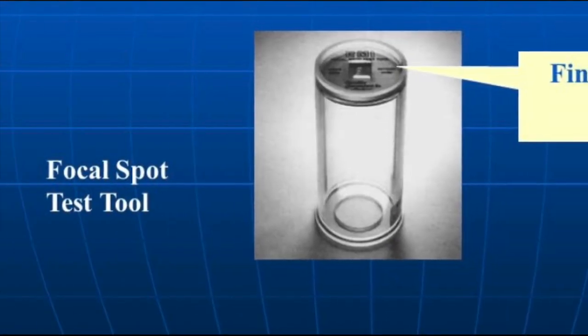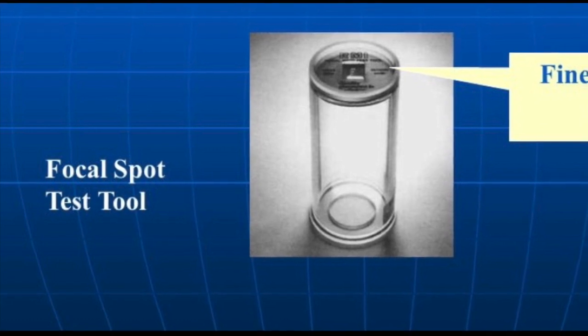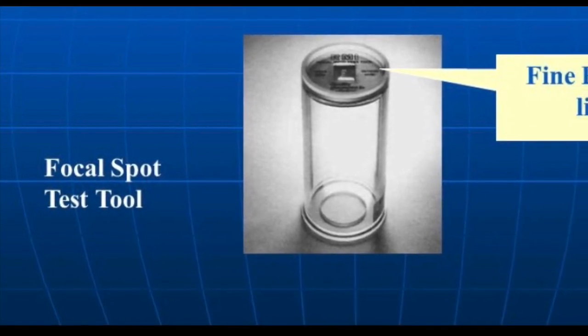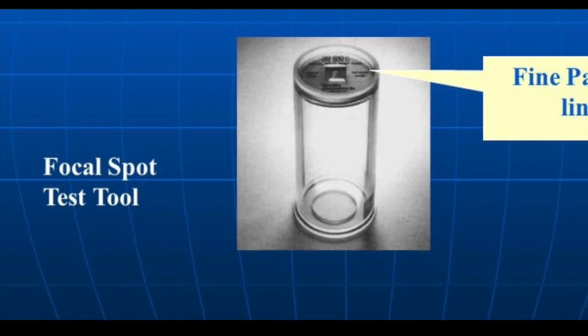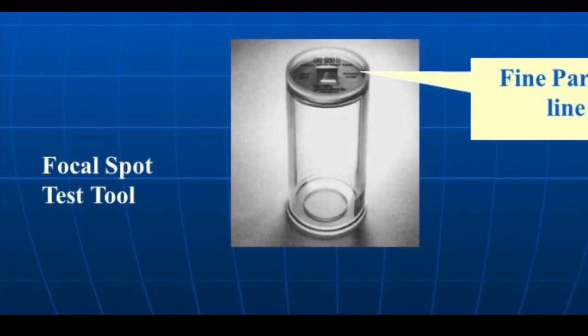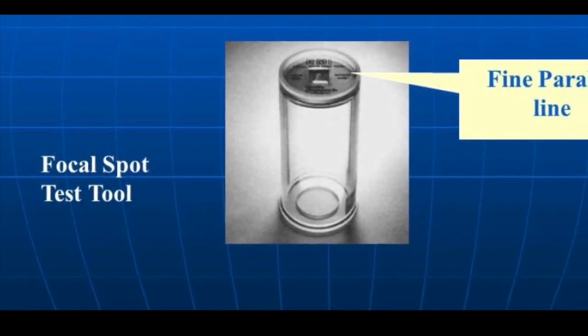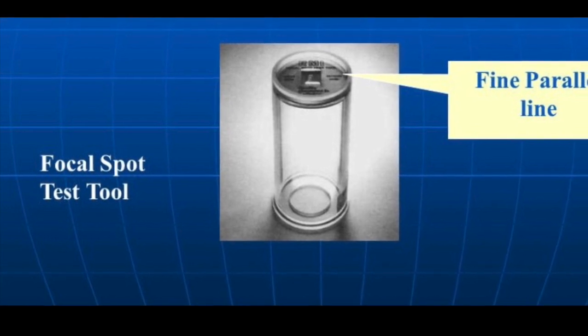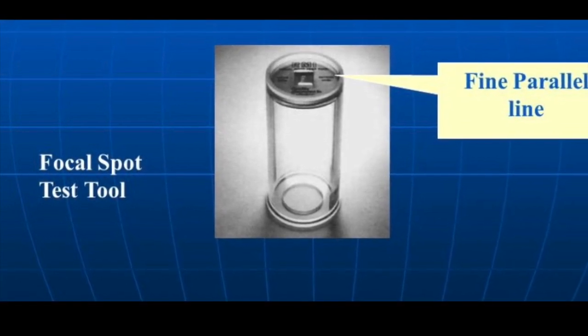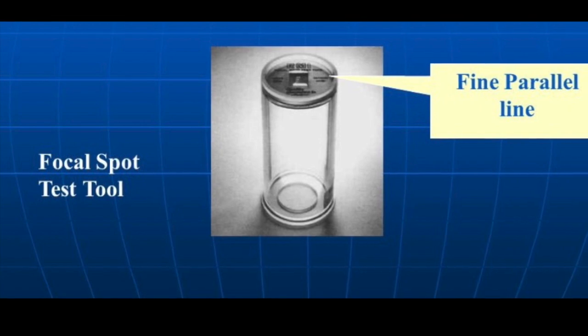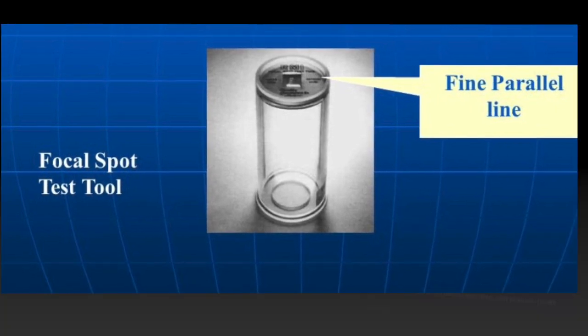Testing the integrity of the focal spot size should be done regularly in order to yield expected results and maximize image detail, as the focal spot size can increase with normal aging of the equipment. There are various tools that have traditionally been integral in testing focal spots when using film. These include a pinhole camera, a slit camera, and a star pattern resolution device.